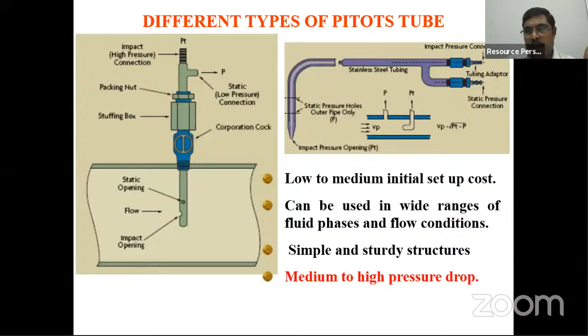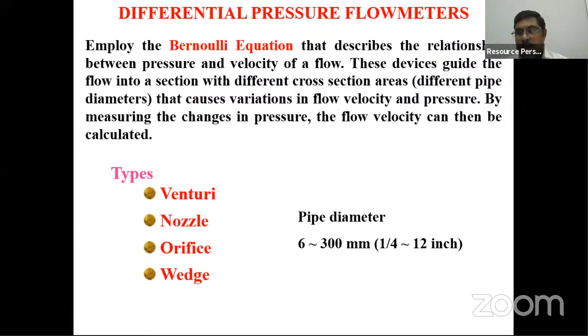Okay, so now coming to the differential pressure flow meter. Here the flow is measured by measuring the difference in pressure between two locations. You allow the flow to go through a change in cross section. When the flow goes through a change in cross section, there will be a pressure change. By measuring the pressure change, you can measure the flow by applying the simple Bernoulli's equation. The equation is very simple to see here. You see here, there are sections 1 and 2. There is a change in cross section. So when the flow goes from 1 to 2, because of the change in cross section, its velocity will change.